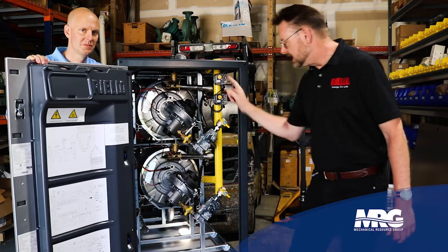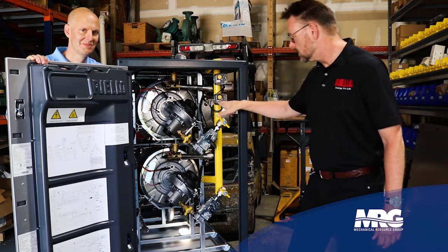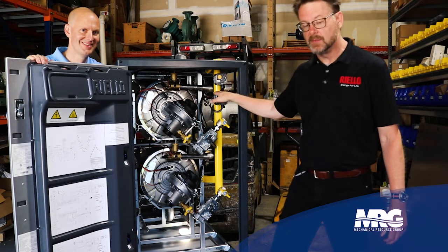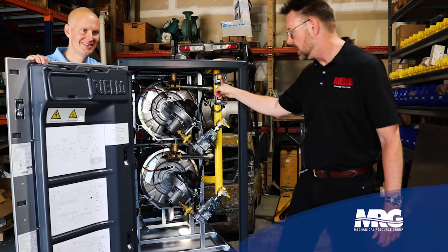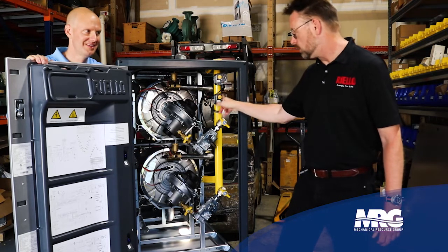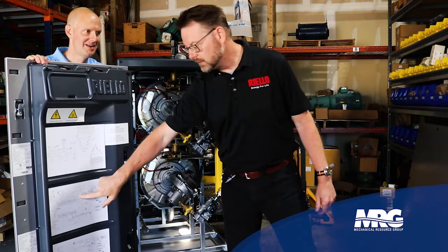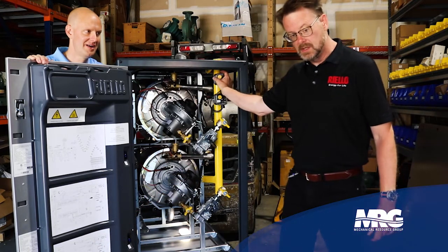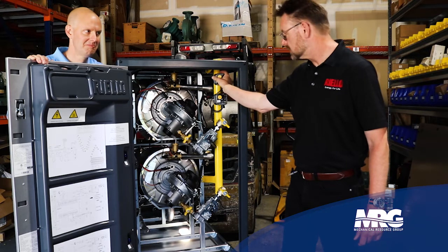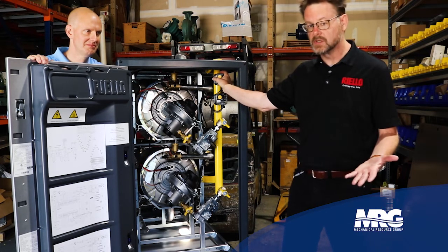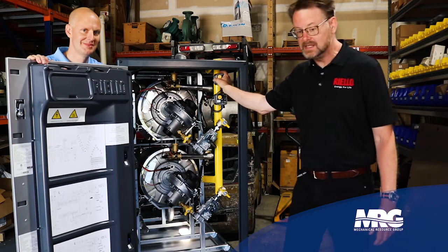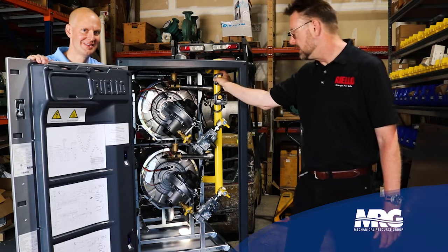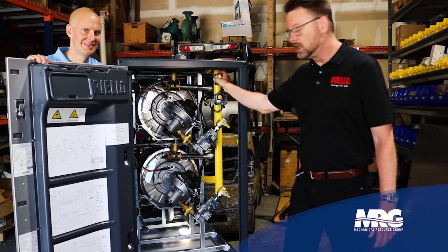Case in point, each of the heat engines does not have its own maximum and minimum gas pressure switches that help us have confidence that the gas pressure is at least in an operable range. Those reside here on the common gas manifold. The failure of one of these switches would be reported through the managing controller to the dependent controllers, that we are concerned either that we have an over gas pressure scenario, or, in the absence of excessive gas pressure, that this switch has gotten flaky and has given us trouble. A flaky switch would need to be replaced. Regrettably, in the case of this flaky switch, the unit would not operate.